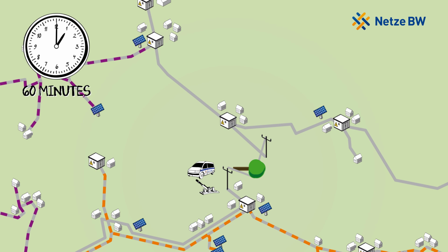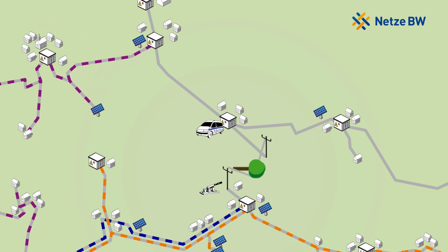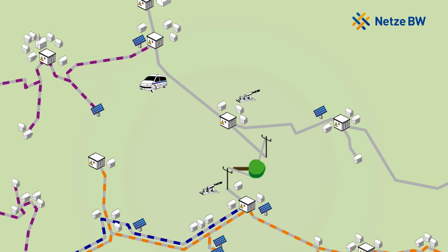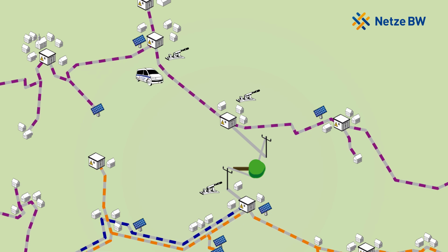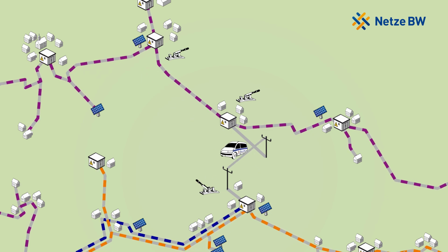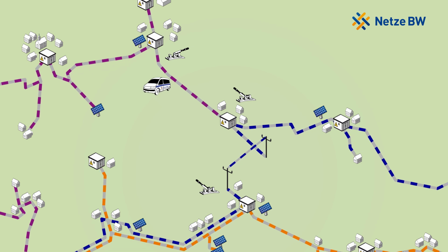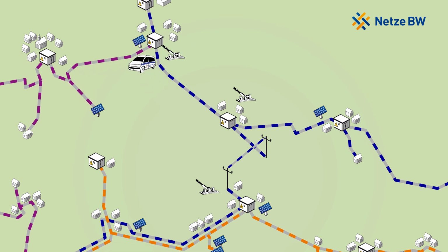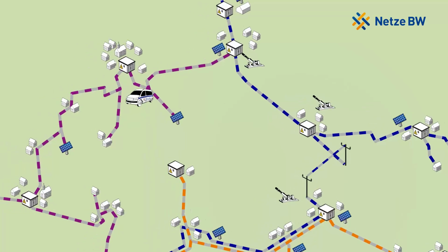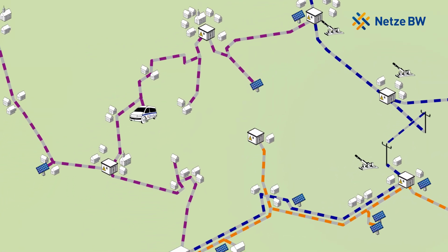Switchover operations in the grid enable the technician to isolate the fault location and establish power supply to the customers via alternative feed routes. The faulty line can then subsequently be repaired. Especially in the case of large networks like the one in Niederstetten, searching for and isolating fault locations can be a very time-intensive undertaking.